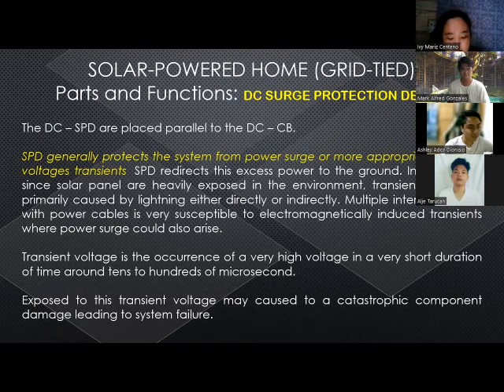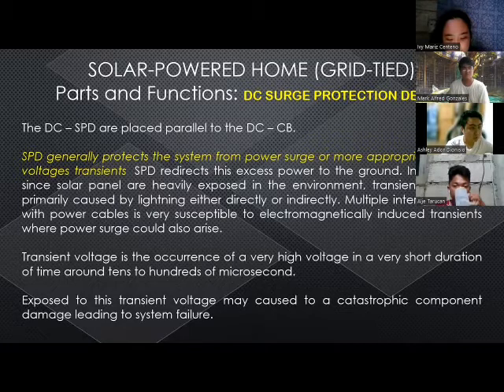Next is solar powered home grid tied. DC surge protection device. The DC SPD are placed parallel to the DC CB. So, SPD generally protects the system from power surge, or more appropriately called voltage transient. So, the DC SPD offers protection. It protects the system against power surge. So, what do we call a power surge? A power surge is the transient voltage that we usually get from catastrophic events, like lightning. Because of that we get transient voltage, or a sudden rise in voltage, which can damage our systems.